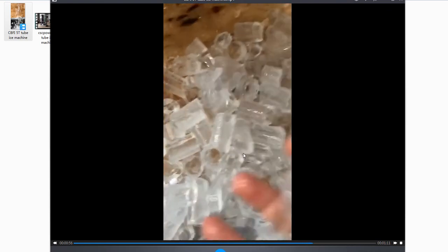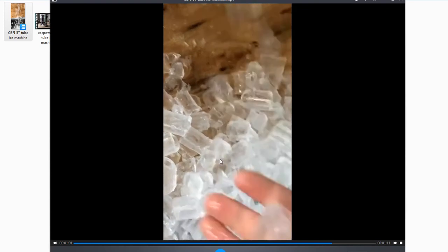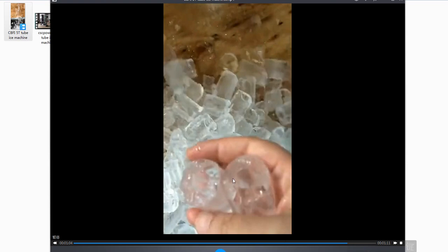The ice is not 100% transparent crystal — it's not beautiful at all, and it has a very large hole, so the ice is easily crushed. The reason the ice is milky white is because the system's evaporating temperature is always out of control — it's always very low, so the water freezes very rapidly and the air bubbles cannot be released from the water as it freezes.